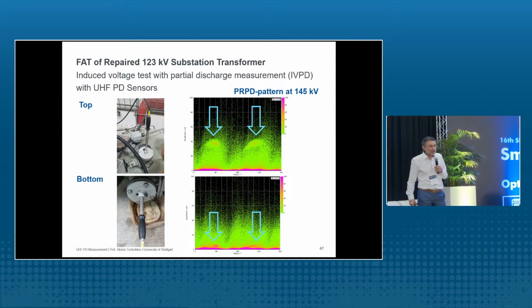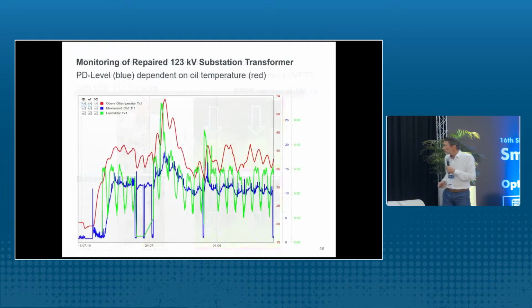And then of course there was a question: oh, we have internal PD on this repair transformer. What should we do now? Can we bring it back into operation? And then the operator said, okay, then I want to have a monitoring of these PD, so that in case the PD is getting stronger, we can switch off the transformer. So we installed the PD monitoring system.